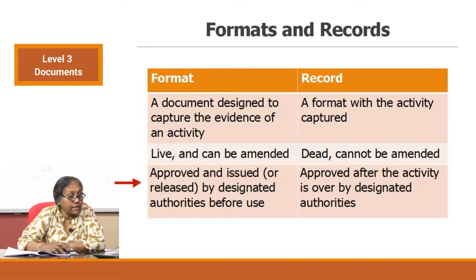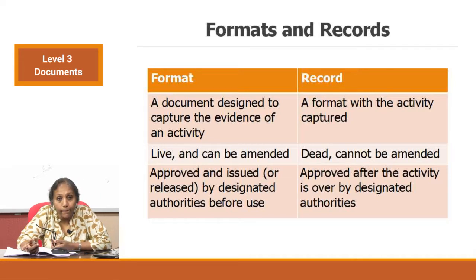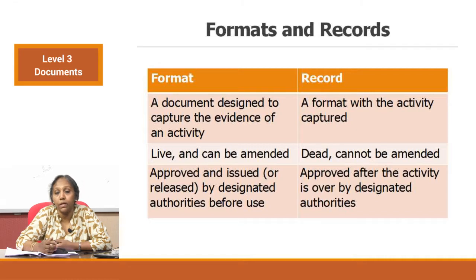Formats are approved and issued by the designated authority before use, and records are approved after the activity is over by the designated authority. For example, if you want to capture quality control results, a format has to be designed and approved by the appropriate authorities and issued to the laboratory technician. After running the QC, the results are documented and brought to the technical supervisory staff who signs it. So approval happens before the activity for formats, and after the activity for records, but in two different ways.